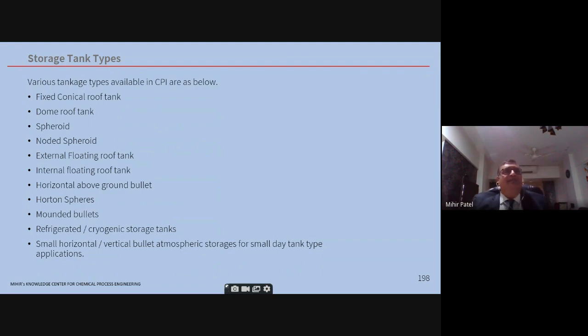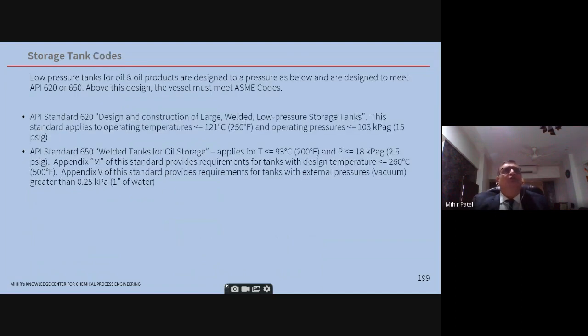Refrigerated cryogenic storage tanks are used, for example, for liquid ammonia, which is stored at -33 degrees centigrade. That is stored in a double-walled cryogenic storage tank. Same for cryogenic propane, cryogenic ethylene, cryogenic LNG. These are all stored in cryogenic storage tanks. Storage tank codes: here you see API 620 and API 650. Normally water tanks in the oil and gas industry are as per API 650, and most chemical tanks otherwise will fall into the API 620 category.